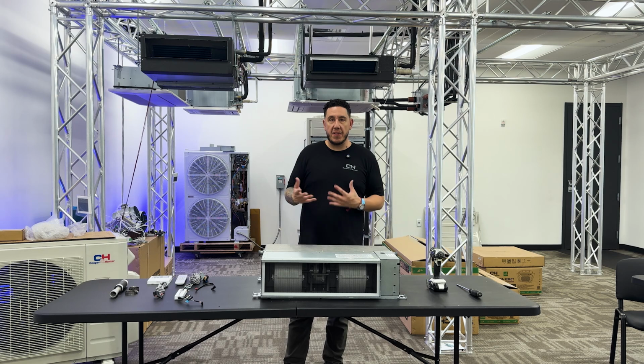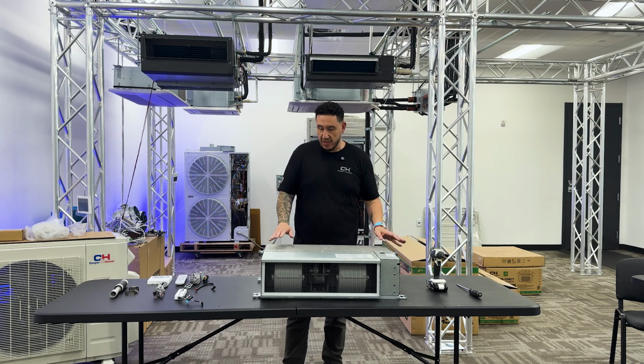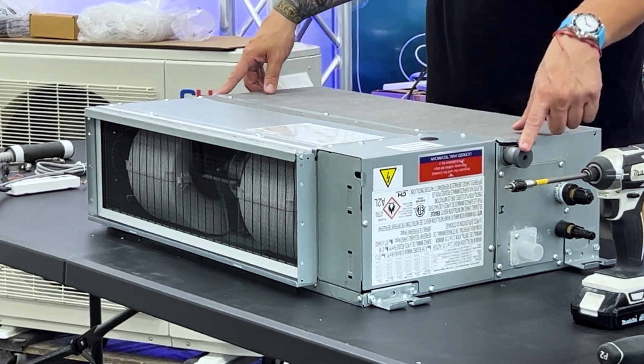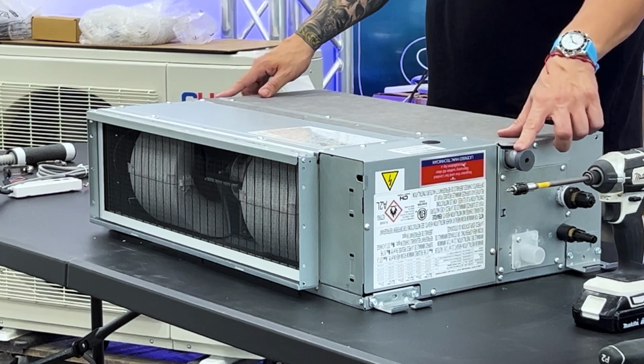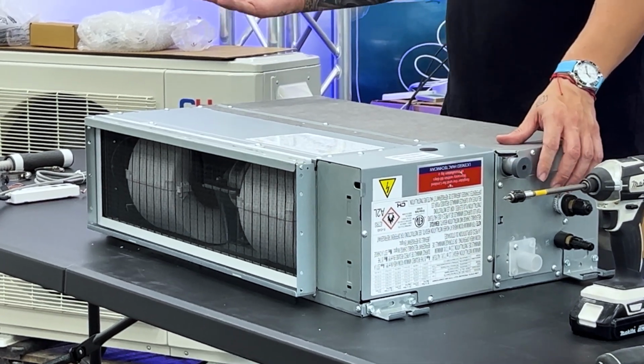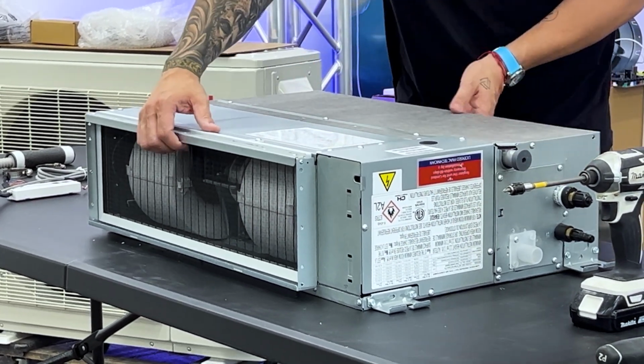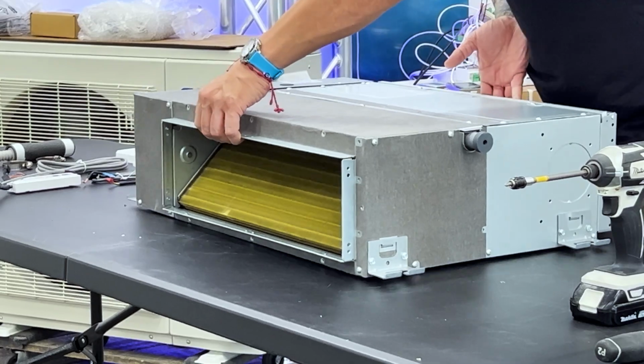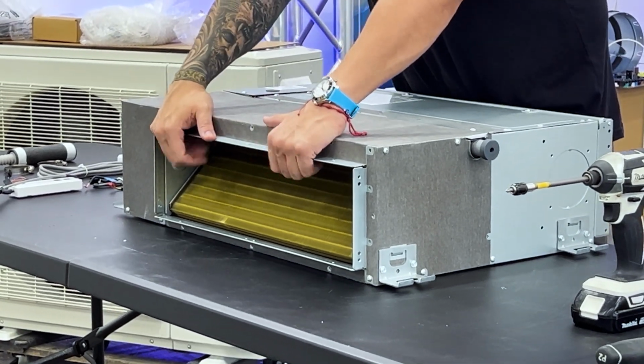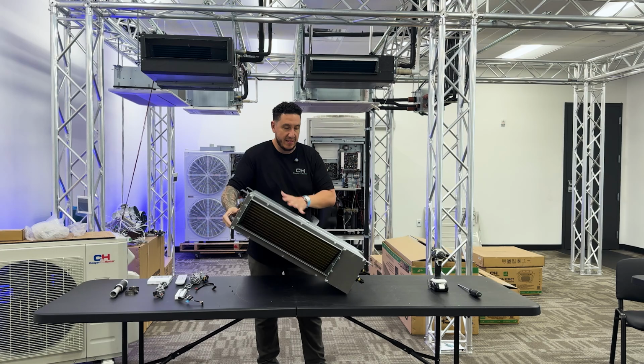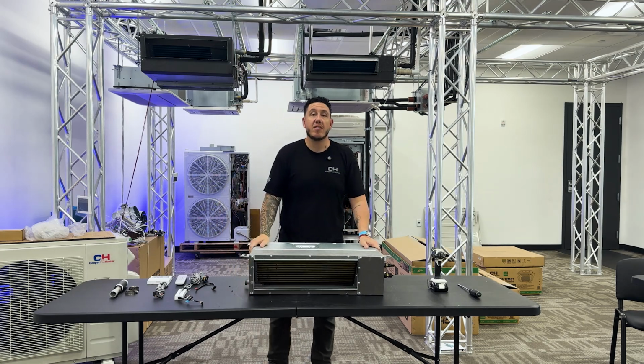How can you tell if this unit is right side up? Guys, it's real simple. Right over here, I have my gravity drains, and that is usually your drain pan, which is supposed to be the lowest point of the system. So if I turn this around, I feel my drain pan is right here. That tells me my system should be installed like so.